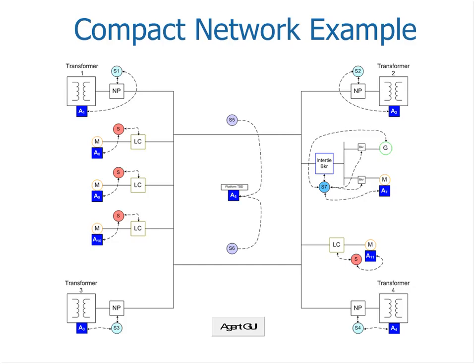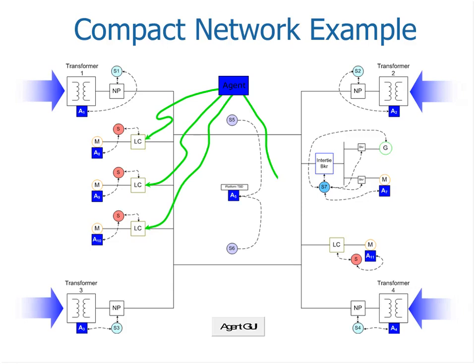What we're talking about is surgically going into the network and identifying that the transformer right around the corner of this compact network is overheating, and it's going to either blow up or reduce its asset life. We can monitor those transformers with agents and communicate that to the agents representing the buildings, single or multiple. That agent can then talk to the individual loads in the building and say we need to ramp down the load on this circuit to reduce load on the transformers. That's a perfect example of using distributed energy resources to modify and impact the grid locally, a more advanced version than just backfeeding power directly in.